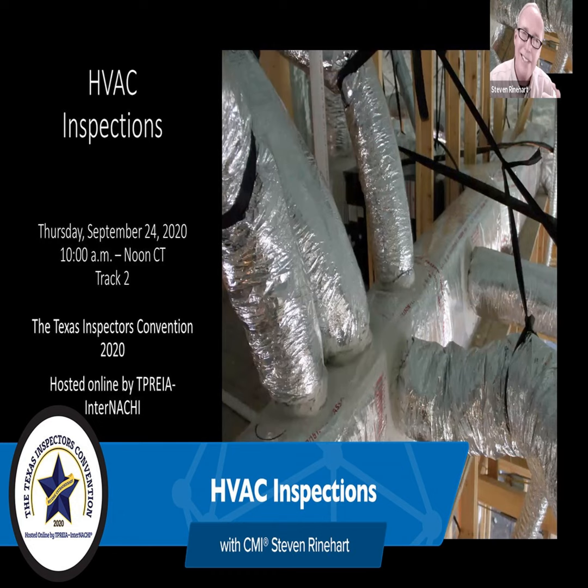I want to be able to provide for that, because if you put it at the minimum 18 inches off the garage floor, and go to the other side of the house, if it's 18 inches off the floor, it's probably on a 2x4. So now we've lost 3.5, 4 inches, and it's probably got base trim. So now we've lost another 3 or 4 inches. So now we've got a return opening that's only 5 inches tall. And this thing whistles like a NASA wind tunnel because it's not breathing.